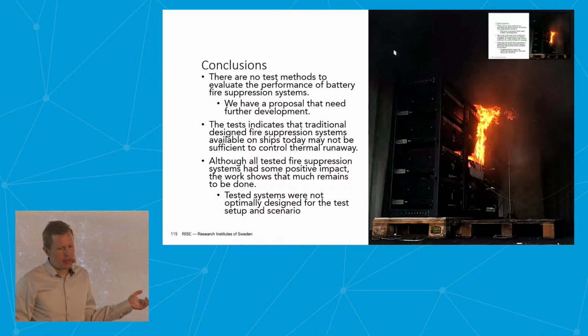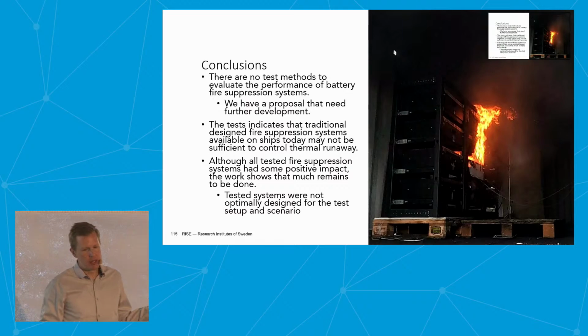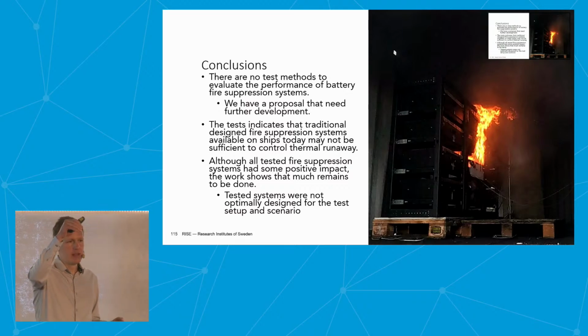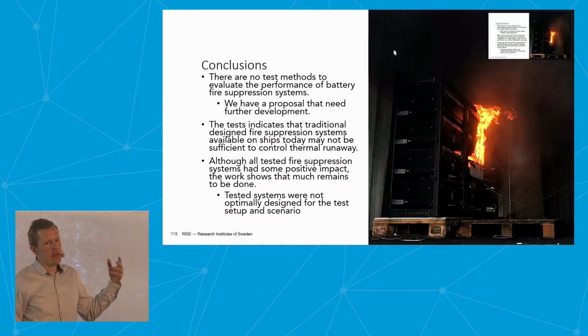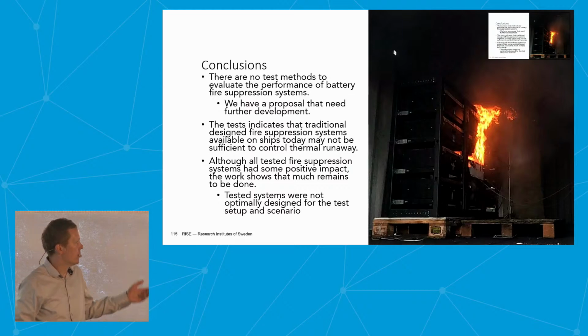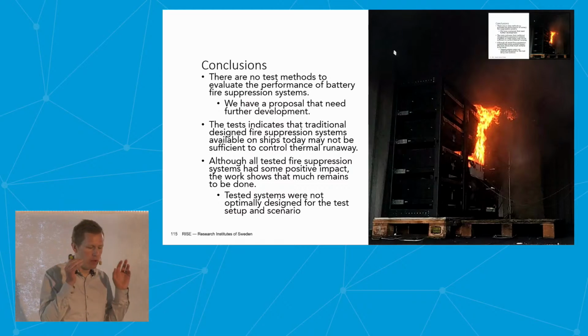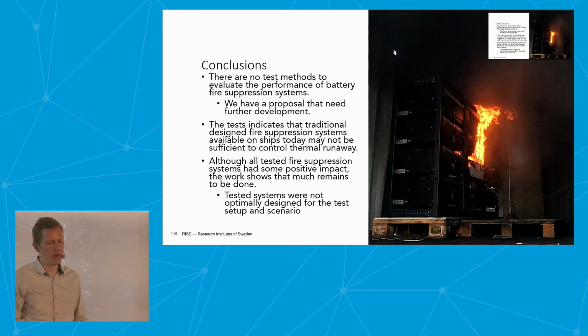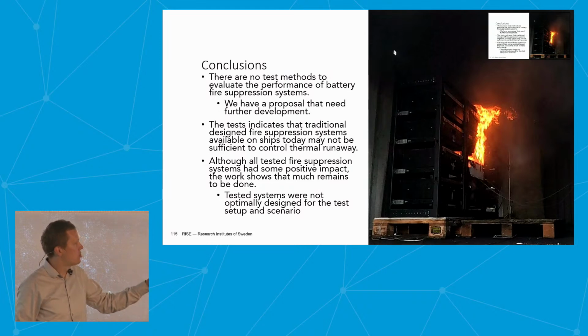The test indicates that a traditional design fire suppression system—meaning in the ceiling, the standard sprinkler—on its own will not be enough to control thermal runaway. So you have to have more specifically designed systems or other passive means to stop propagation. But all systems had some positive impact, though more work has to be done. And as I said in the beginning, they were not optimally designed, so they could perform better if better designed.